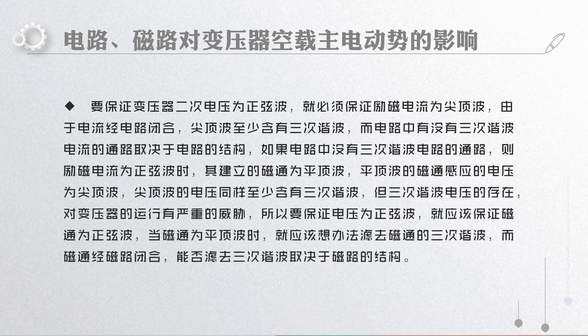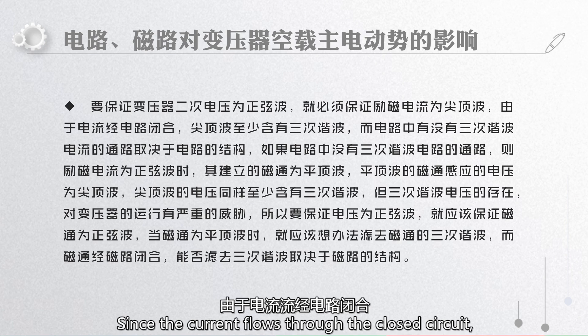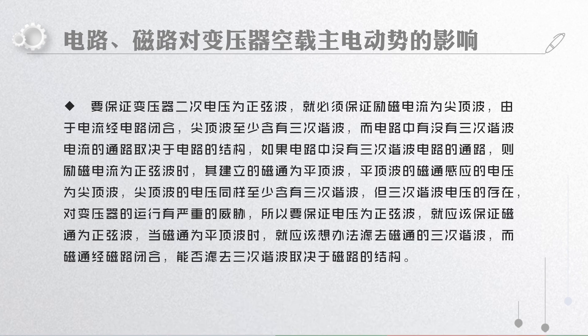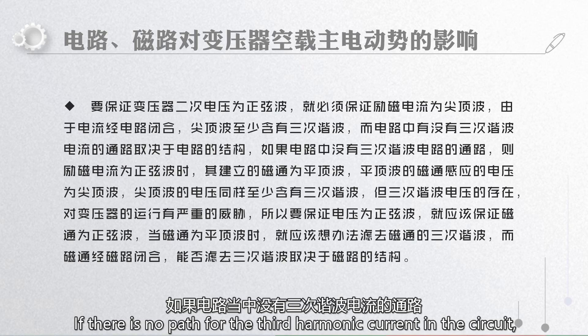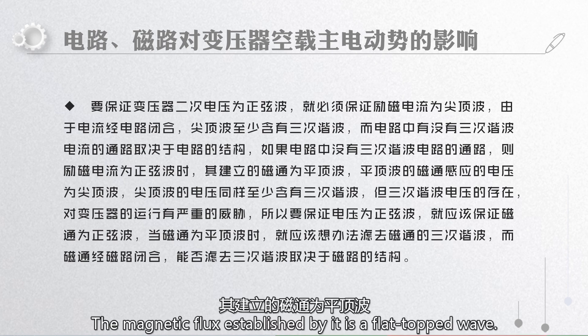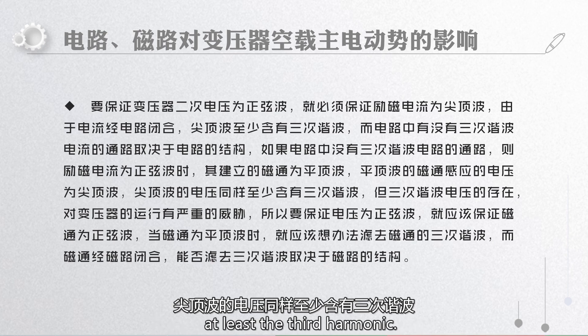The meaning of these two conclusions is that to ensure the voltage on the secondary side of the transformer is a sine wave, the excitation current must be a peaked wave, since the current flows through the closed circuit. The peaked wave contains at least the third harmonic. Whether there is a path for the third harmonic current in the circuit depends on the circuit structure. If there is no path for the third harmonic current, the excitation current is a sine wave, the magnetic flux established by it is a flat-topped wave, and the voltage induced by the flat-topped magnetic flux is a peaked wave.